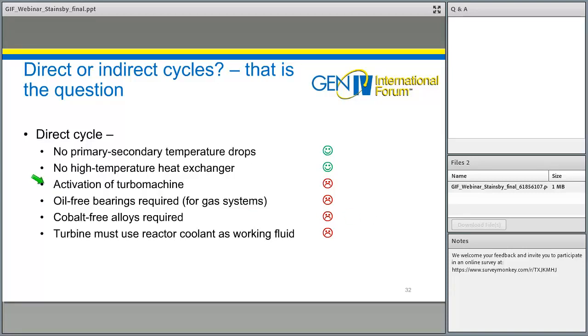Also, turbine alloys generally require a lot of cobalt for things like stellite hard facings or hot hardness in gas turbines. If we put those in a reactor circuit, we've got to keep the cobalt out, because it becomes very radioactive if it passes through the reactor core.